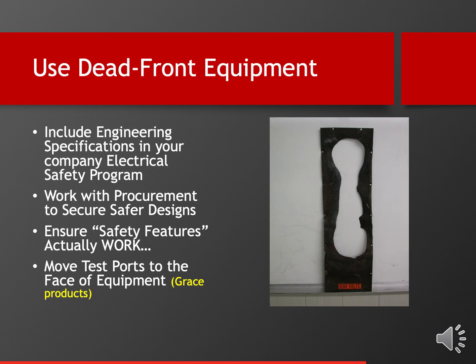And I put Grace products there in parentheses because that's a huge benefit of using these products, is that you can work through a dead front. So don't get me wrong, that dead front that you see in the picture there used up a bunch of energy to melt that steel. So the situation was better for whoever was on the other side of it. But in this particular case, the arc lasted so long that there was enough residual energy that the heat was, I think, that caused the fatality, if I'm not mistaken, in this event. Let's go to the next slide.